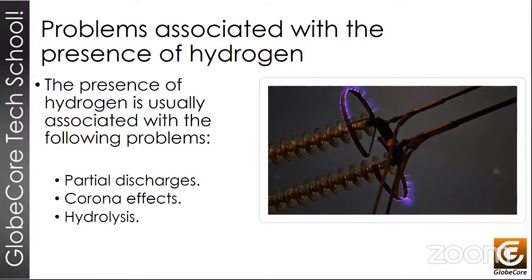The corona effect is an electrical discharge that occurs due to ionization of gas that surrounds conductors, where the potential gradient exceeds a certain threshold. This effect is usually observed on power lines with voltages around 30 kilovolts per centimeter. Partial discharges are incomplete electrical arcs or discharges, and all of these are large generators of hydrogen. These are some typical transformer problems that need to be addressed whenever we see them in order to increase the service life of the transformer units.